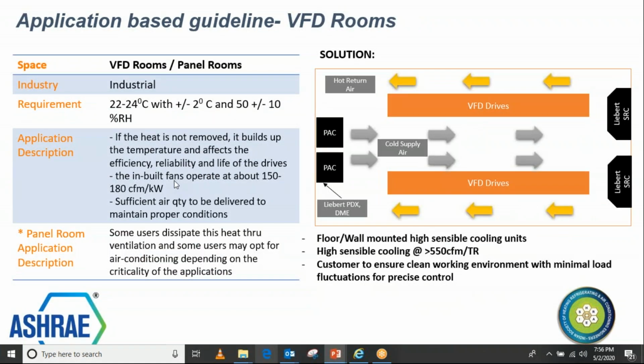VFD and panel rooms, control rooms, most of you may be very familiar with. Here again there is an electrical load and less human occupancy in all of these rooms, so it's very important that you maintain a good filtration level here also, to avoid PCB failures or this kind of electrical failures. Earlier we used to hear that VFD doesn't really require precision cooling, but our experience in industry says that if you are able to use precision AC, the life of the VFD panels will be much higher. Your overall control room will work more smoothly. Your downtime will be much lower. So the cost of the downtime, the cost of the equipment, and the life put together obviously make precision AC the choice for VFD rooms.